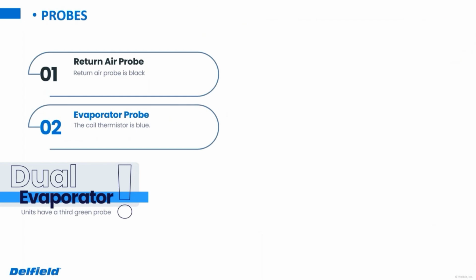As far as the probes go, as Bud had mentioned before, we'll mention it one more time for those that may have missed it. The return air probe is going to be black, plugs into S1 on the control. The evaporator probe, if you just have a single evaporator, you'll have one probe for that. It's going to be blue, plugs into S2 on the control. And then if you have a unit that has a dual evaporator setup, you're going to have an additional evaporator probe. That'll go into the evaporator furthest from the condensing unit. That's going to be a green probe, and that'll plug into the S3 terminal on the control.